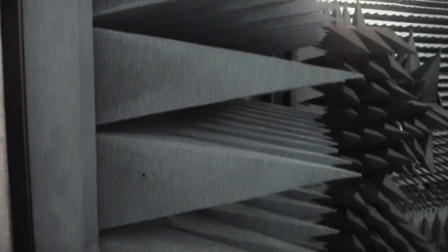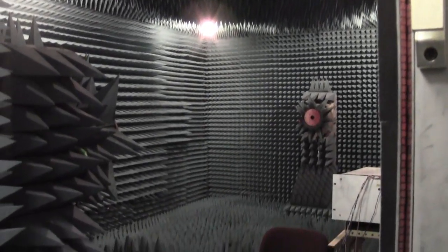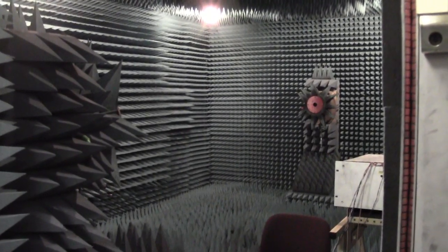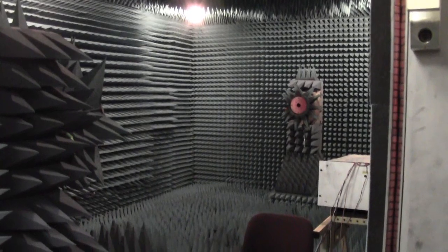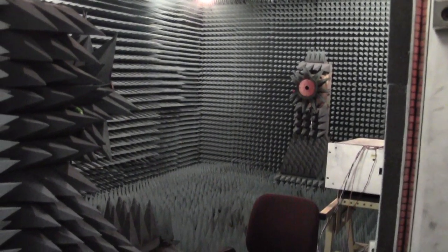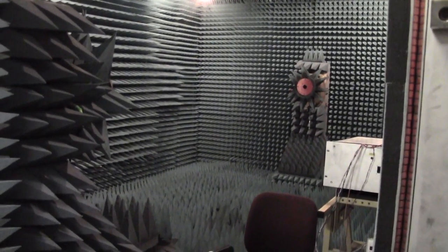And yeah, you can see a profile view of the RAM there. It's a specific size for absorbing microwaves and stops any microwaves from being reflected back. So not only does it screen, it also stops reflections and everything else, so you can get a nice proper pure characterization of your transmitters and your receivers. And there we have it.